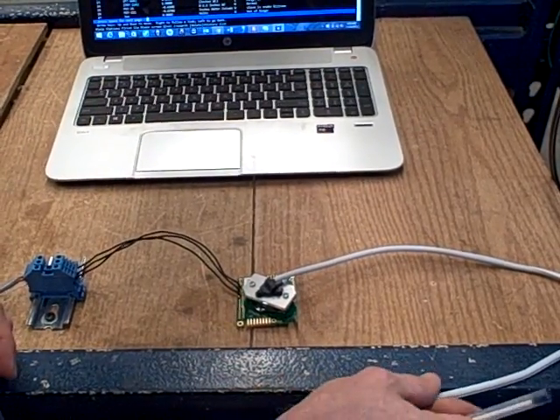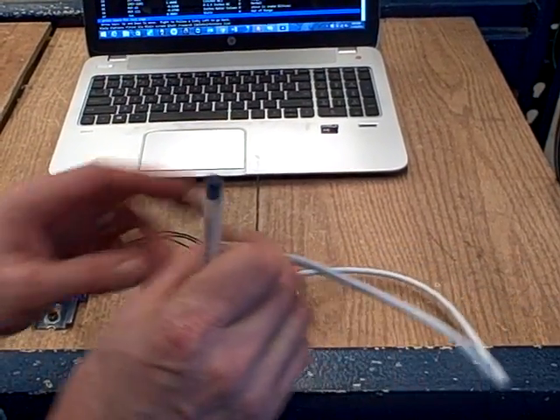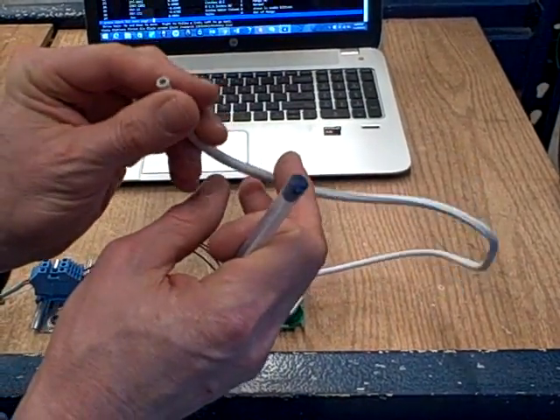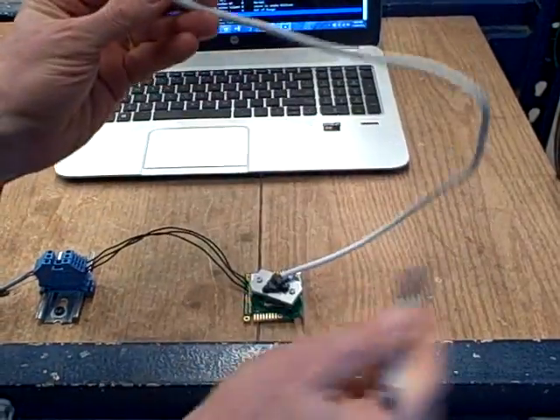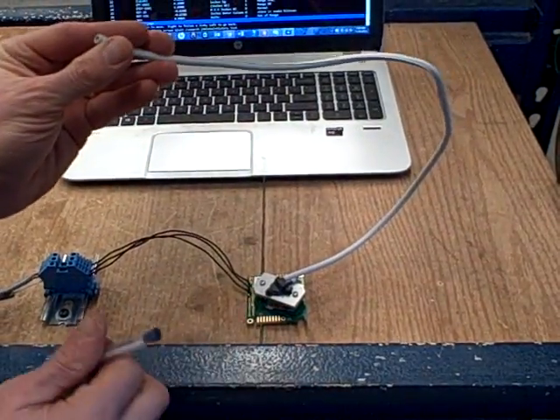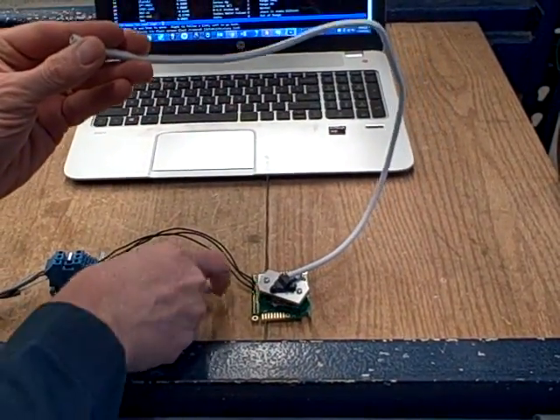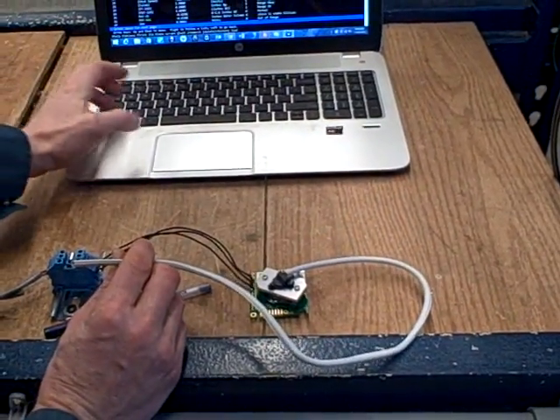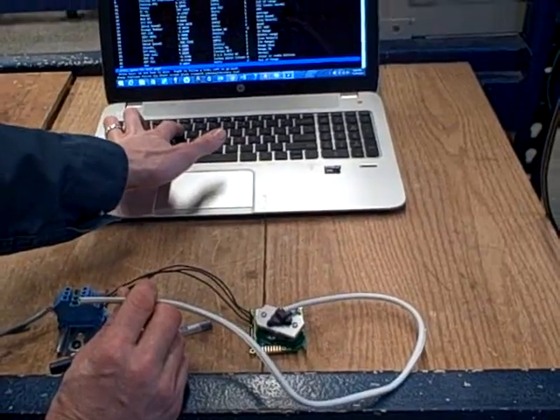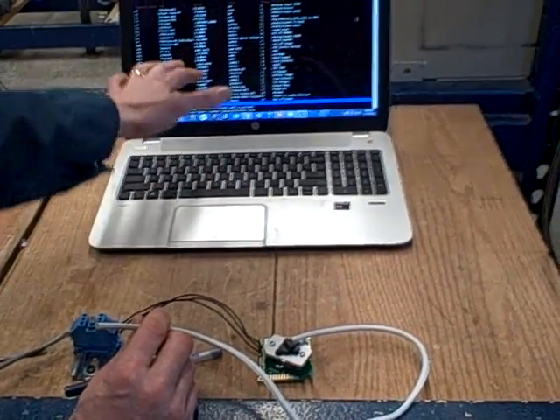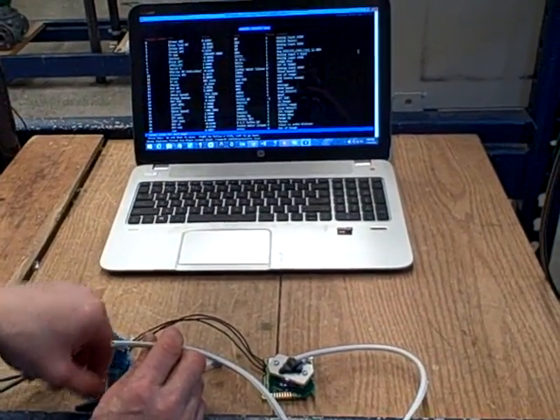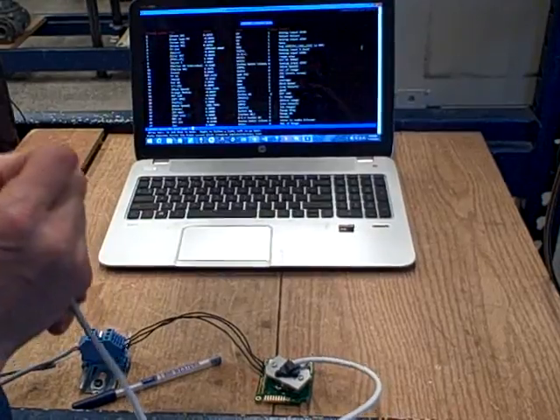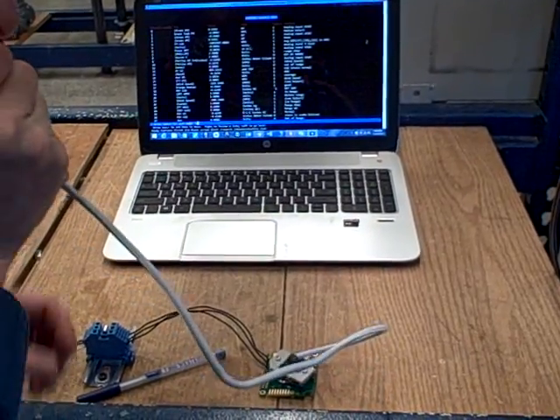So we can demonstrate quickly how we can drive this to a higher signal level. I'm going to intentionally blow some air from my mouth through this tube, and we'll see how the sensor reads. I'll occasionally have to hit control R here to refresh the web browser to look at our CO2 reading, and as I do this, we'll see the reading go up.